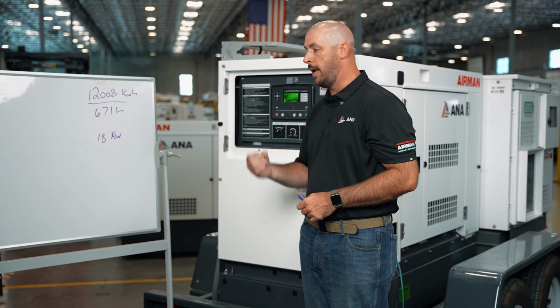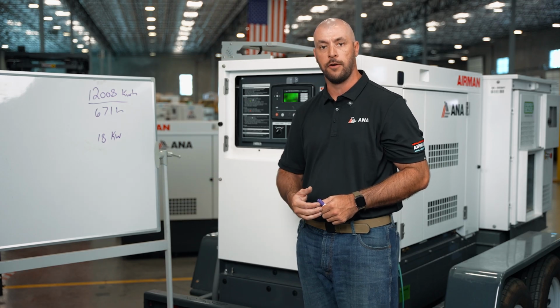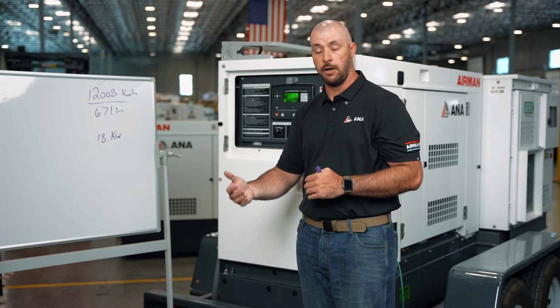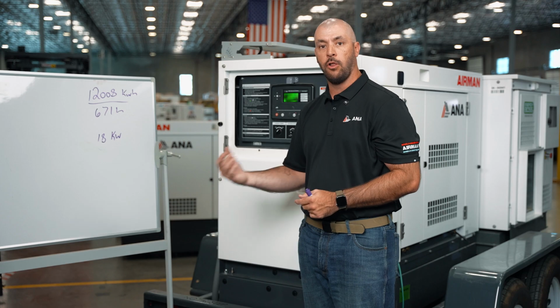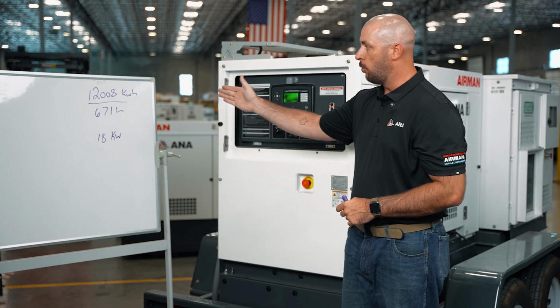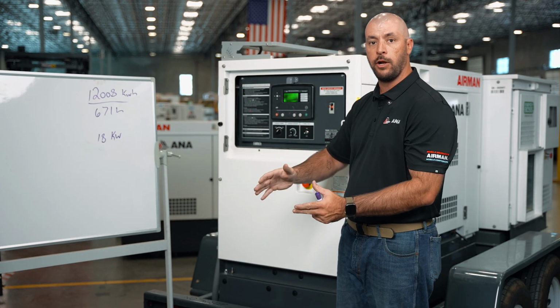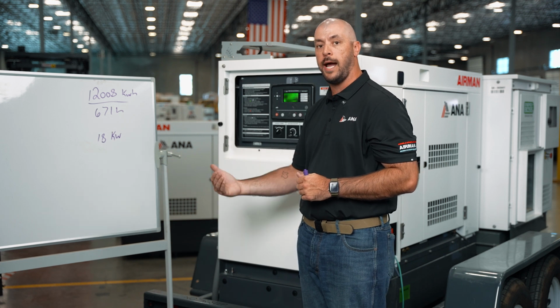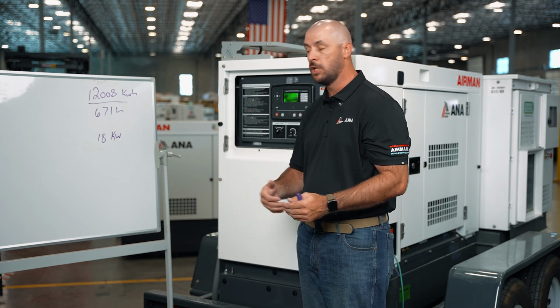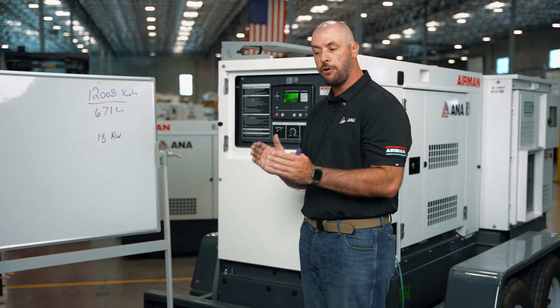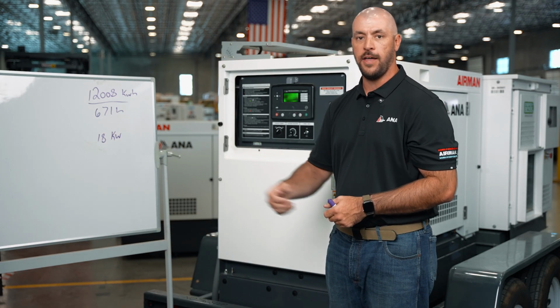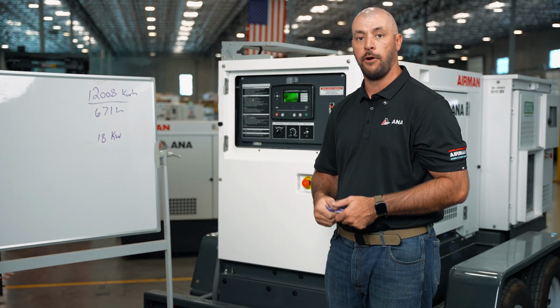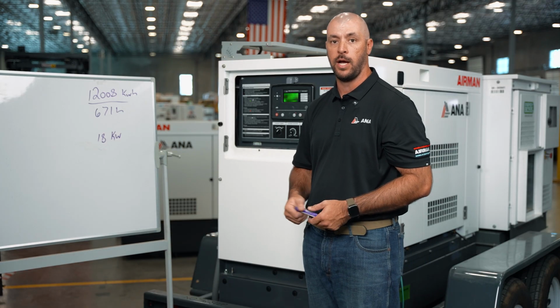And what we really recommend is whenever those units come back in for service and they're doing their data logs on them, you should write down this kilowatt information. That way you have the details from where the generator was. So when it goes out on the next rental and comes back, you can subtract your new kilowatt hours from your old ones, and your new engine hours from your old ones, and you can find out the exact load that the last rental put on your generator and what may need to be done maintenance-wise for it.